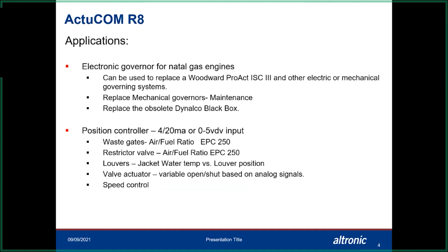Well, we've been testing this thing for some years now, and I checked with our repair department, and this is very minimum of anything that's even come in. So just speaking on that wastegate control, that's a good application to add with your EPC 250. If you're quoting an EPC 250, instead of adding the I2P into your panel and then maybe going out and outsourcing a new valve or something that's going to control that wastegate, you have a product right here that will work in that application.